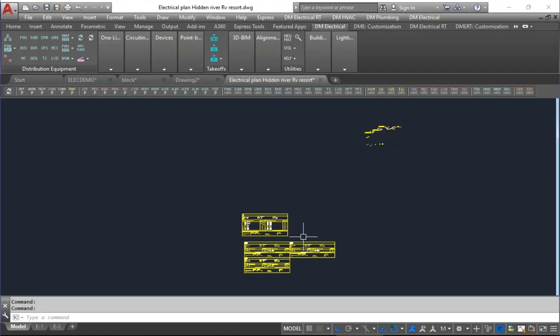So to model it properly, you need to model each of the pedestals as an individual panel. It's closer to an apartment complex where you've got multiple apartments, one for each RV, which is close to what an RV is, a small traveling apartment. So each of those pedestals actually needs to be modeled as a separate piece of distribution equipment. Since they're very similar, typically a recurring panel template would be the right way to do it. So you'd create a template and then create an instance for each RV site.